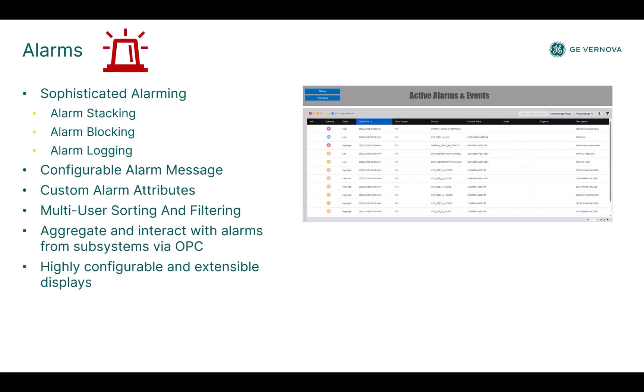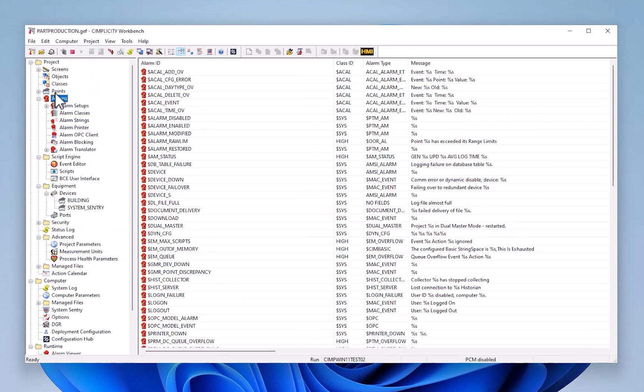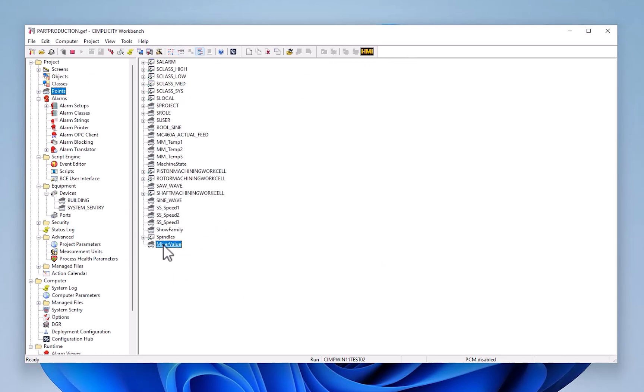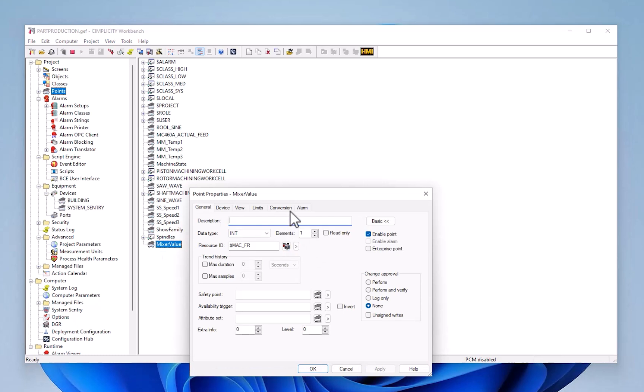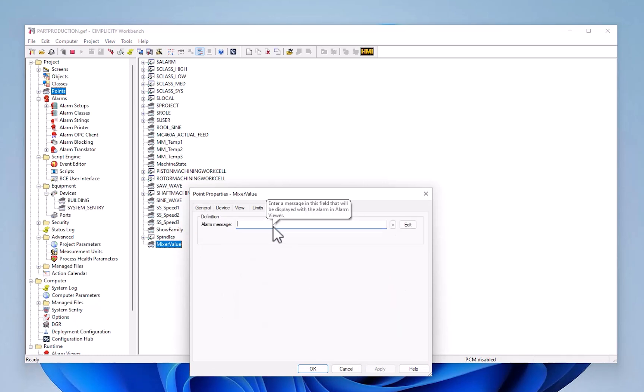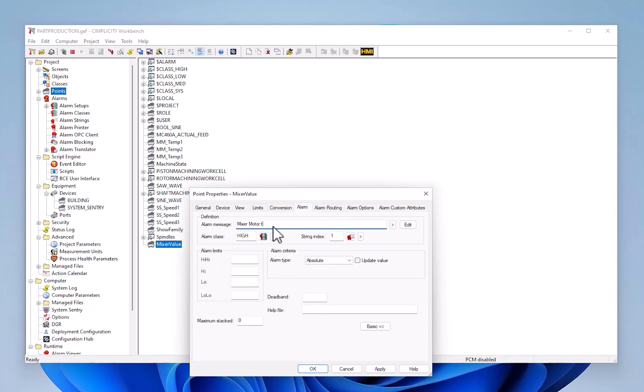CIMPLICITY provides extensive alarm support for detecting and displaying abnormalities in your process, configured on your CIMPLICITY measurement points as they come in from devices or are internally calculated. You can configure alarms on a given point — for example, on our mixer value, we go to the alarm tab and create an alarm message: "Mixer motor too hot." Since we're looking at mixer temperature, too hot would be over 105 degrees Celsius. You can configure a multitude of options for this.